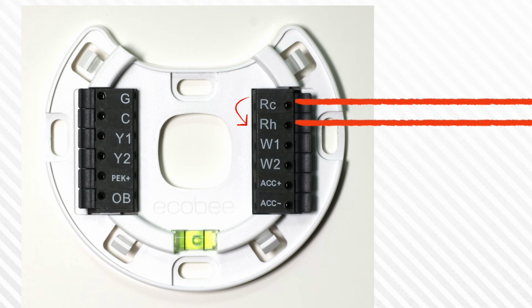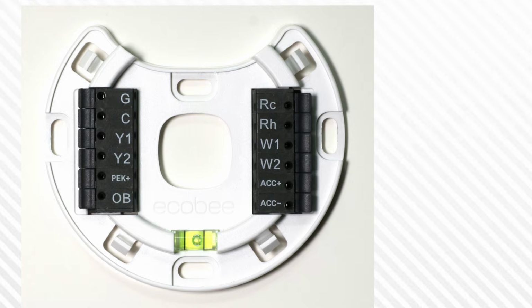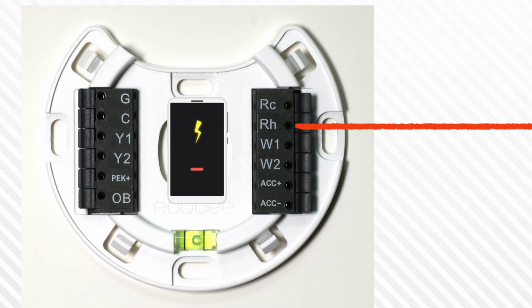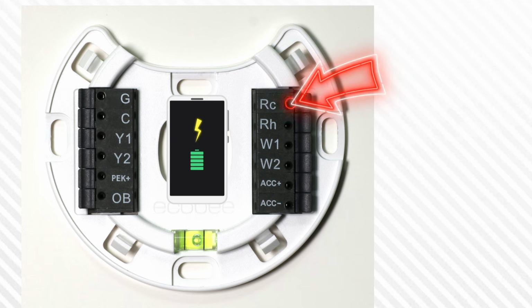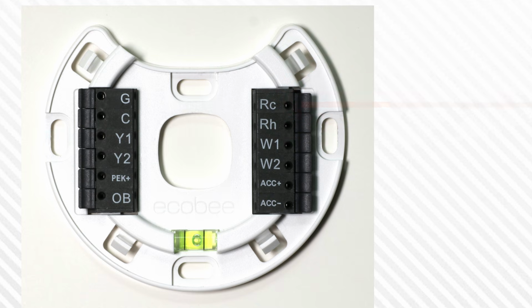One of the common mistakes I see that leaves a lot of people scratching their heads is when they're hooking up a heat-only system and they naturally presume that the wire needs to land on that RH terminal. What many people don't realize is that all smart thermostats charge their internal batteries off of the RC terminal, even if you're just running heating. So unless you're running two completely separate systems, always land that wire on RC.